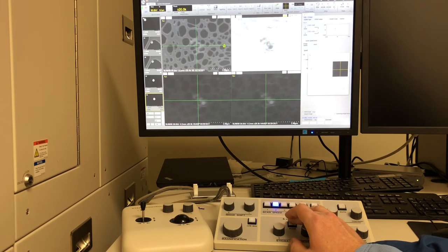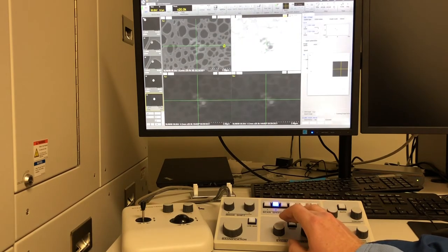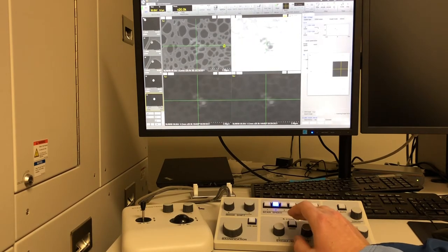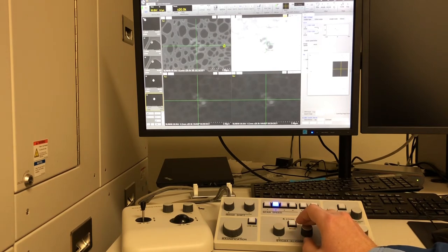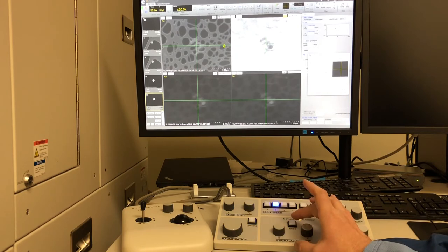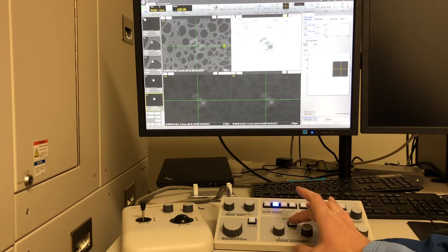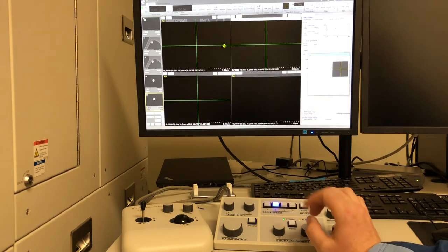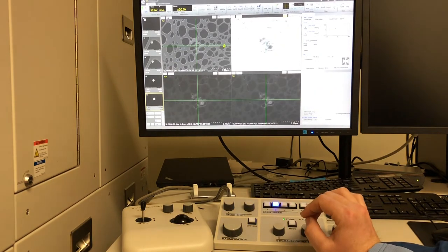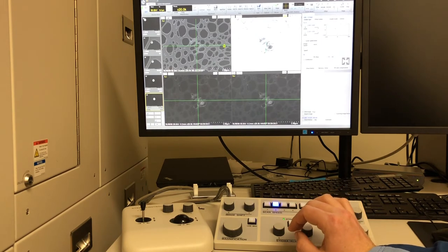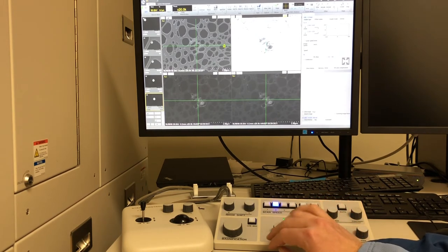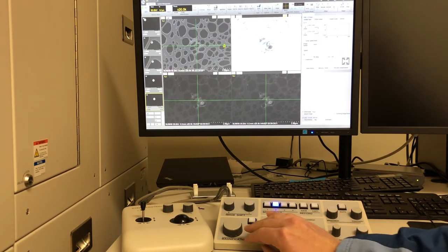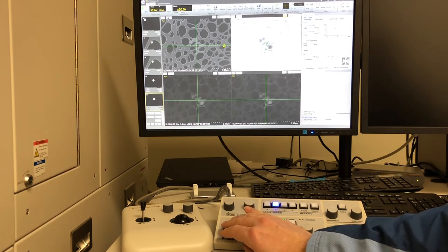I'm pressing the mode button one more time to do the same thing in the Y direction with the same correction. So again, we're just looking for pulsing. Then we click it one last time in order to end the alignment in the system.